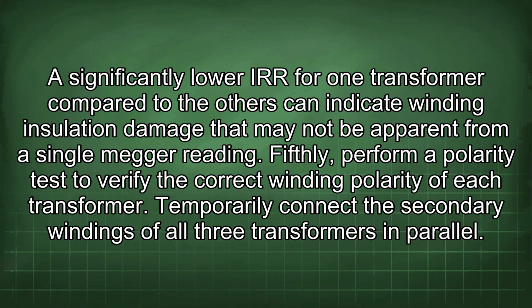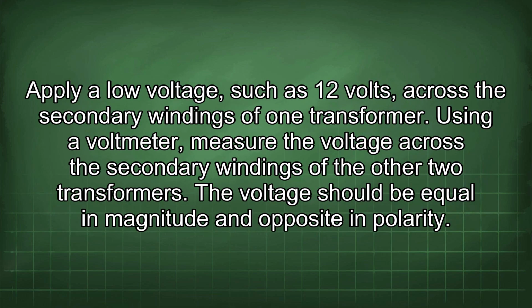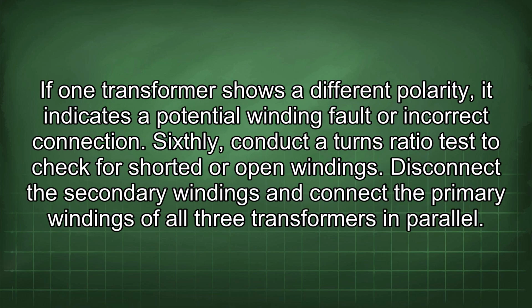A significantly low IRR for one transformer compared to the others can indicate winding insulation damage that may not be apparent from a single megger reading. Fifthly, perform a polarity test to verify the correct winding polarity of each transformer. Temporarily connect the secondary windings of all 3 transformers in parallel. Apply a low voltage, such as 12 volts, across the secondary windings of one transformer. Using a voltmeter, measure the voltage across the secondary windings of the other 2 transformers. The voltage should be equal in magnitude and opposite in polarity. If one transformer shows a different polarity, it indicates a potential winding fault or incorrect connection.